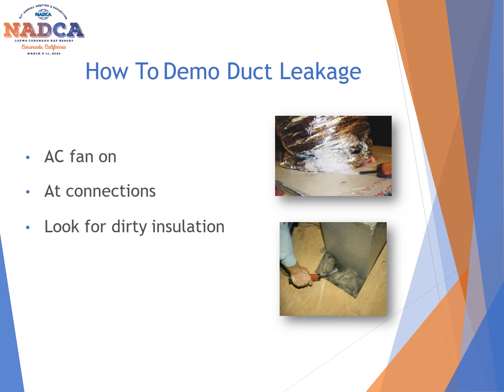So there's a couple different ways you can actually utilize the smoke, but one of the first ways is to start with the AC with the fan actually on and blowing and go around to the different connections. And you can actually, by holding it up to the connections, you can actually see how the air is blowing around. You get up into the attic, you can actually start to see how the air is penetrating and being sucked into the home as well. And the homeowner a lot of times can actually see it being sucked and blown into these spaces as well. So anywhere that you may potentially have a leak, look for dirty insulation. That may be a telltale sign that you have airflow or air movement in that particular area. And so just take a little bit of smoke and watch how it flows, and that will help identify the areas that maybe need to be repaired.